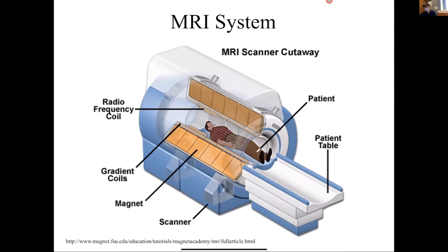This is the basic outline of an MRI system. Most MRI systems are basically big solenoids or big donuts. They look very much like a CT scanner but are generally much larger, because they have a huge coil that creates an immense magnetic field. In an MRI system there are typically three coils to think about: the magnet, which is the big coil generating the biggest magnetic field; gradient coils, which cause spatial variations in the magnetic field; and radio frequency coils.